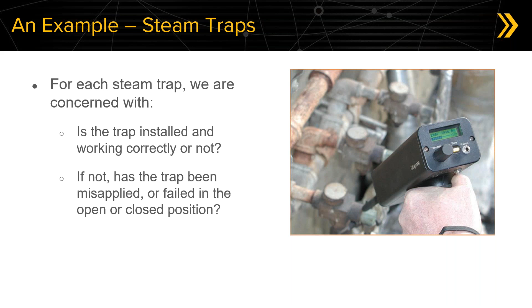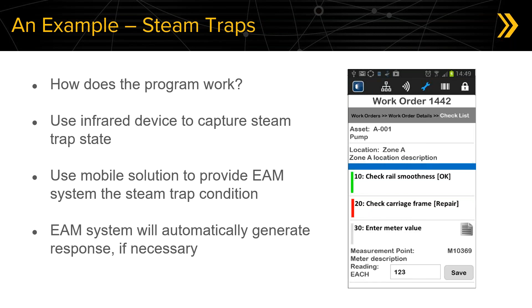So we use the infrared device to capture the steam trap state, and then a mobile solution that connects to our EAM system to record the steam trap condition. Then our EAM system will automatically generate a response if necessary.